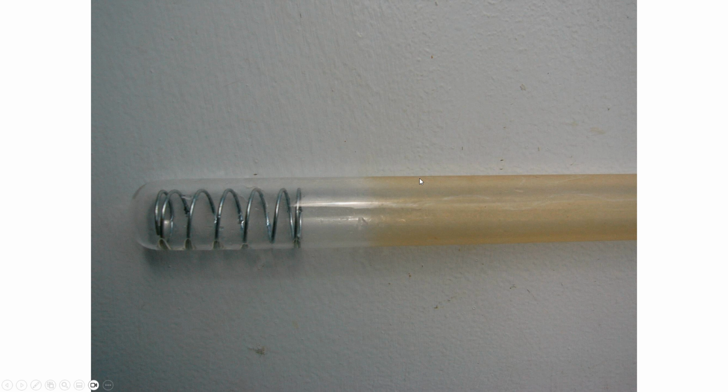This is just a look at the sleeve fouling that can accumulate. It looks like glass, but it's not actually glass. It's made out of quartz. The difference being that quartz can transmit UV, whereas ordinary glass will absorb UV. Like your car window, you don't generally get a sunburn if you're inside of a car.